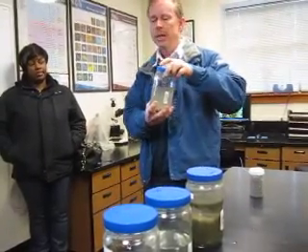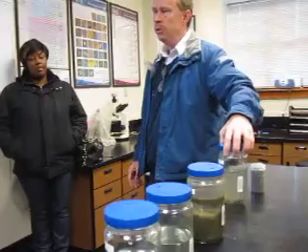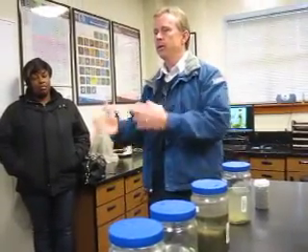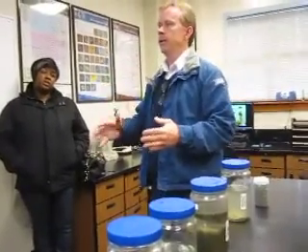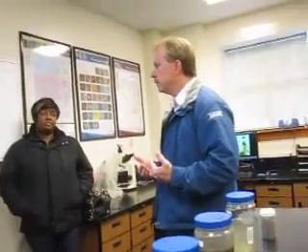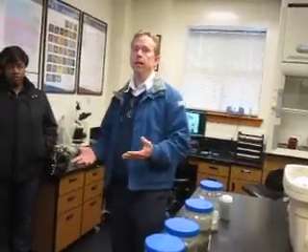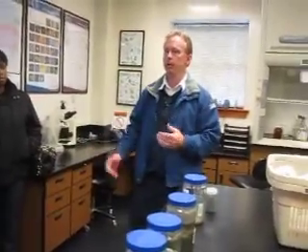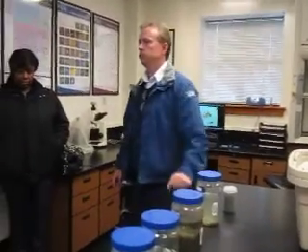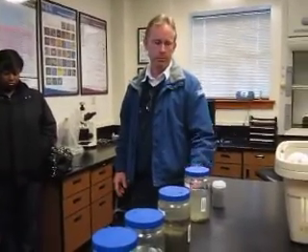The thing about BOD is it's a 5-day test. So when you set up that test, you don't know what the results are for 5 days. It doesn't help us as operators a whole lot. We could be out of compliance and not even know it. But if you run a COD test, you could get that result within 2 or 3 hours. So it's a chemical oxygen demand instead of a biochemical oxygen demand. It's a measure of the depletion of oxygen within that sample, which is very, very helpful for us.